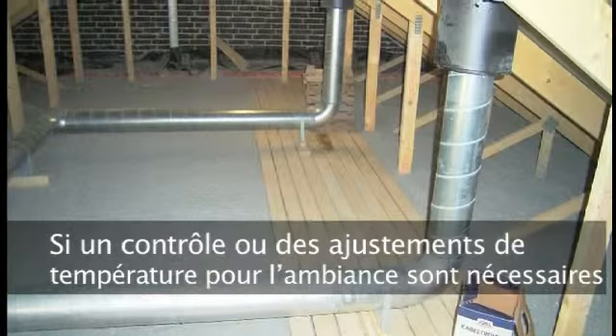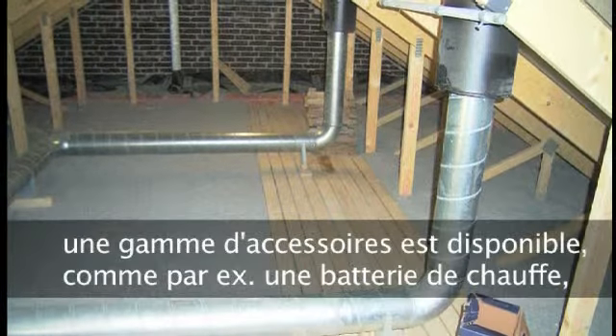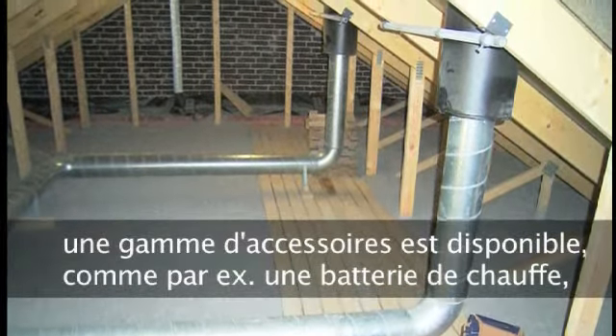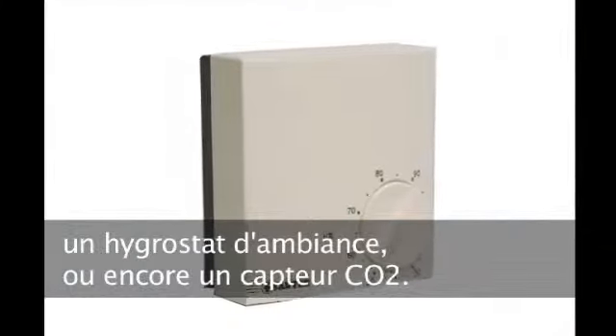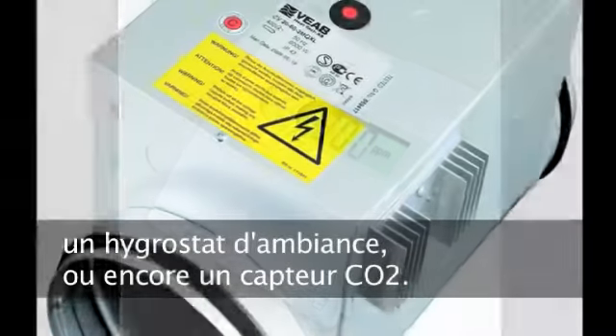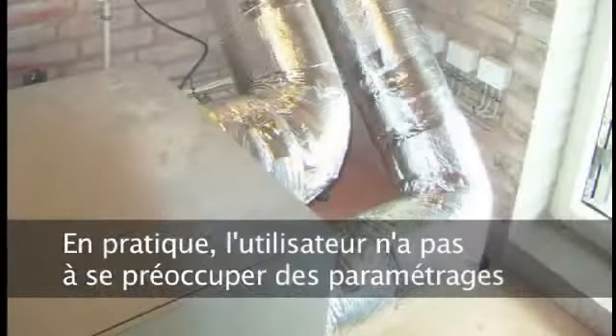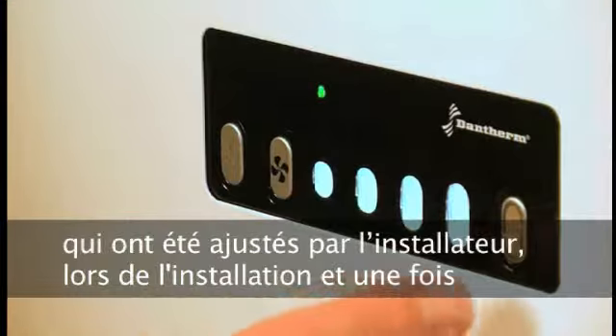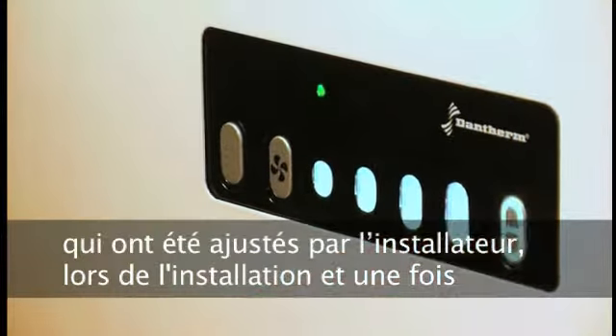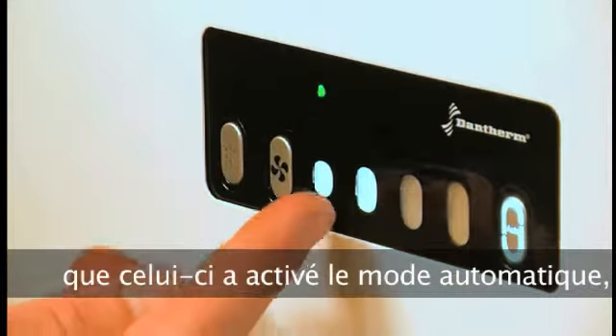If further control or adjustment of the indoor climate is required, a range of accessories is available, such as external hygrostat, CO2 sensor, and pre- and after heaters. In practice, the user never has to think about setting or operating the unit once the installer has adjusted the system and switched on the automatic operation.